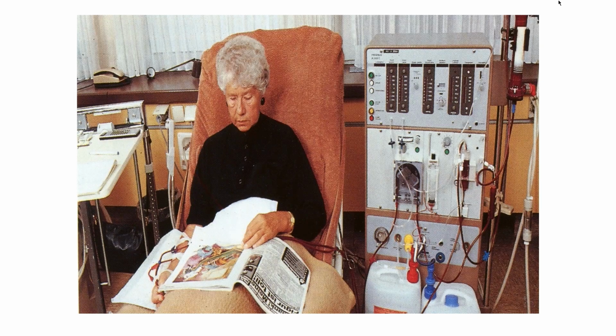When conductivity issues were being experienced, did they call the biomed? What they did was take that cover off. If the conductivity was low, they cranked it up to deliver more acid. Same thing with the bicarbonate, which had one in the back of the machine similar to that. Or the other method they used: my conductivity is alarming, this is easy, I'll go ahead and change the reading. And that happened multiple times on different occasions.